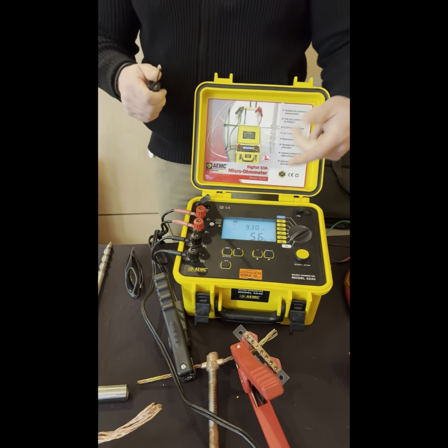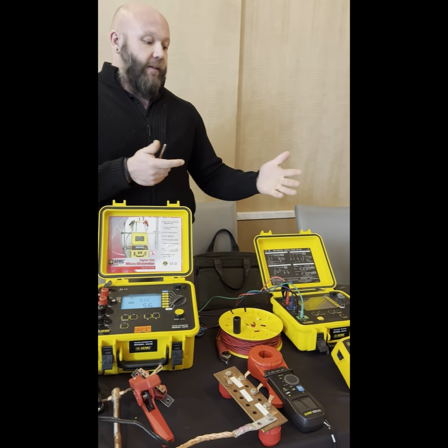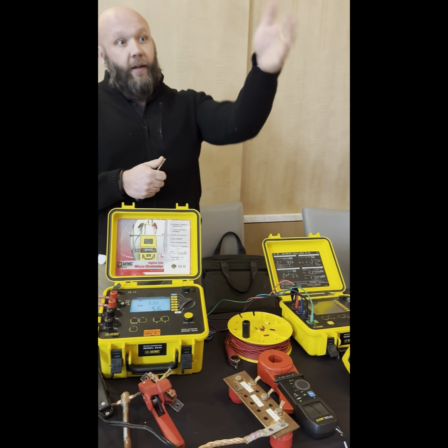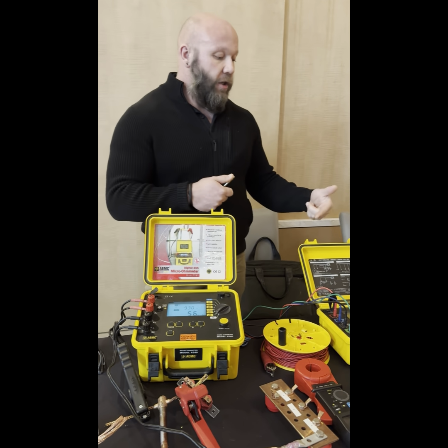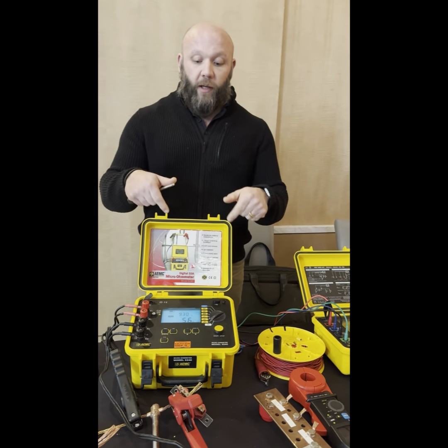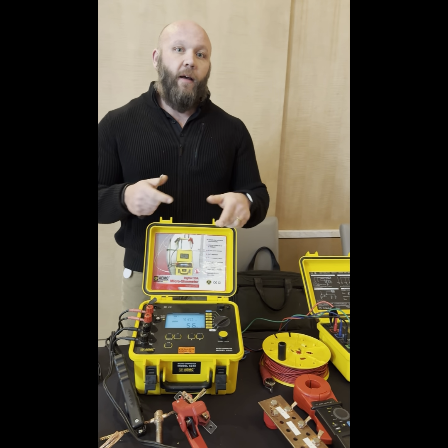And you could apply this to any type of measurement, whether it be fall of potential, and we log that. You know, when I did this annual PM, I did it in the southeast direction, so that when we do this annual PM next year or whenever, we do it in a southeast direction. So think about controlling variables while you're on the site, because there's so many you cannot control.